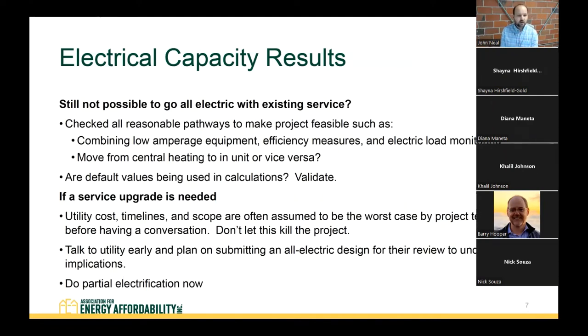So what happens if we do all that and we're still struggling to make it work with the existing service? Double check that we've looked at all those pathways. Look at low amp equipment options, load reduction, efficiency, etc. We've had projects that looked at moving from master metered or central equipment like central heating to in-unit heating, or vice versa, because sometimes that can help shift electrical load, say from fully loaded apartments to a less loaded common area service.